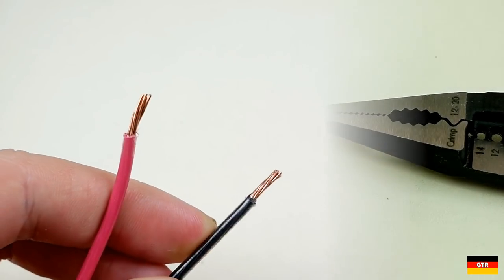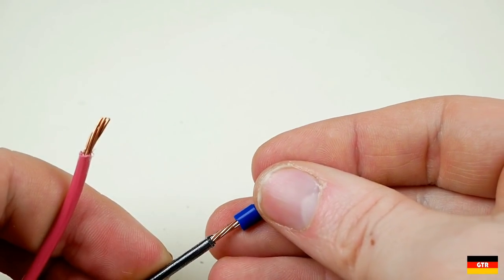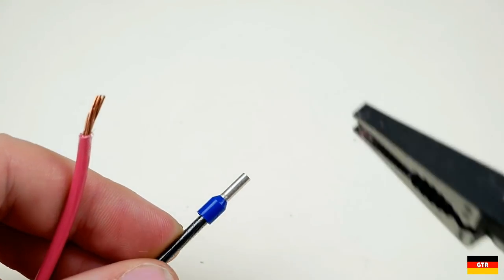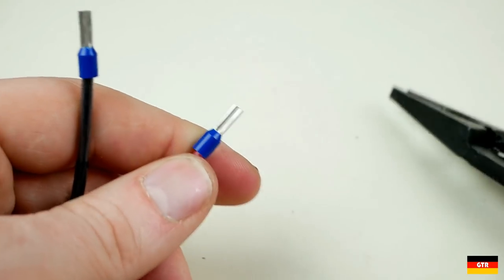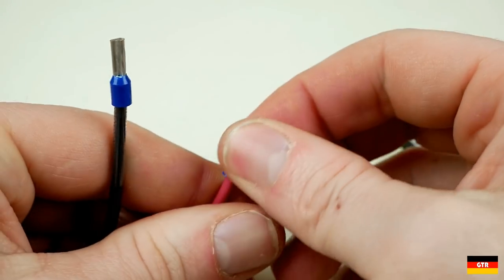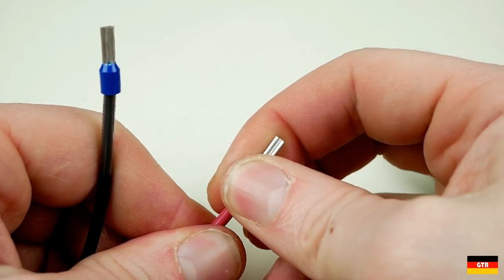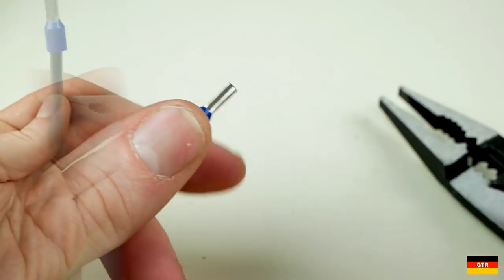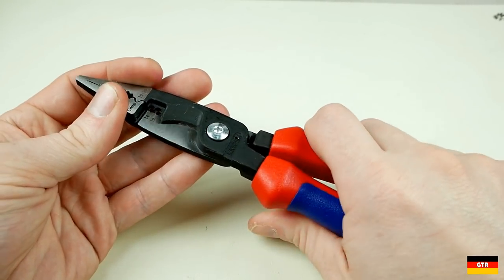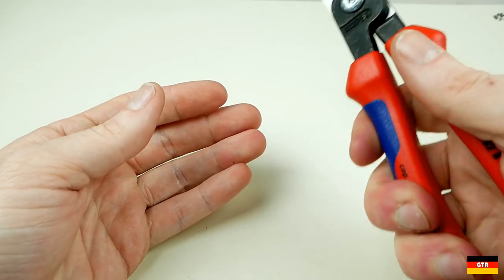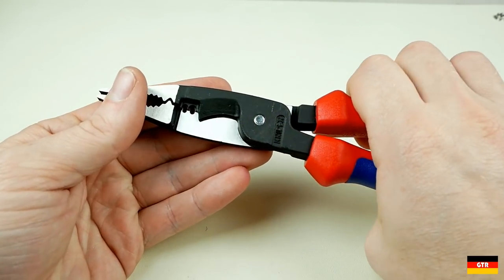I did try this once more with the same wire gauge that had more strands in it and it seemed to crimp a lot better than the one with the thinner strands. Overall I think this did a fine job doing the work of several tools. It is very specialized so it won't be universal for all electrical installation jobs so it really seems to be targeted towards structured building wire and not necessarily industrial control panel installation and maintenance. So some of the electrician viewers will have to give me your opinions as well.